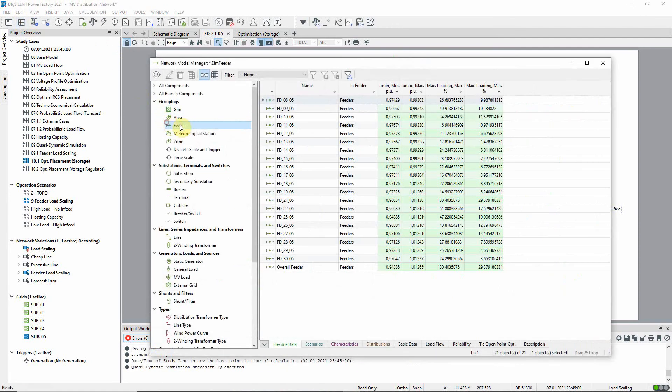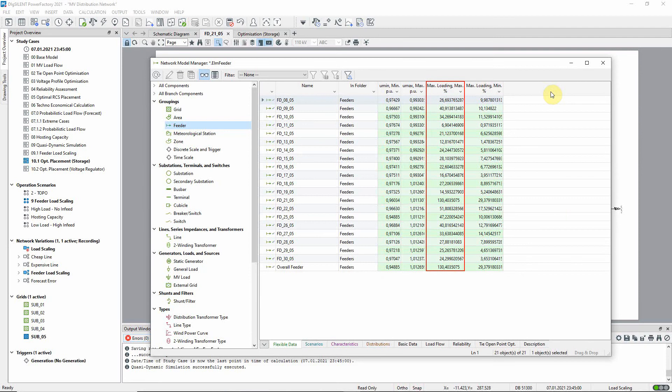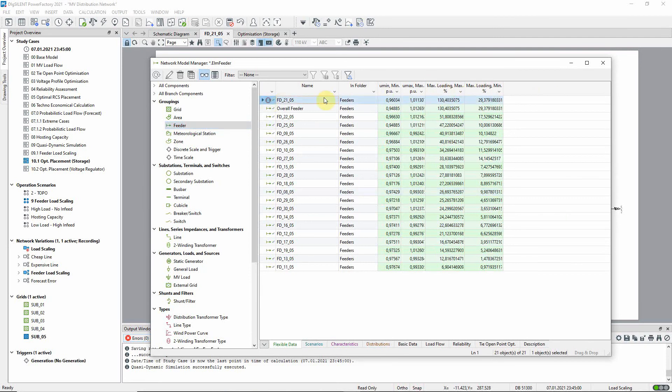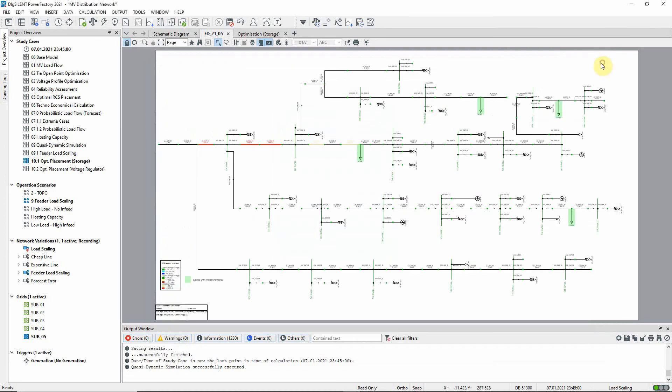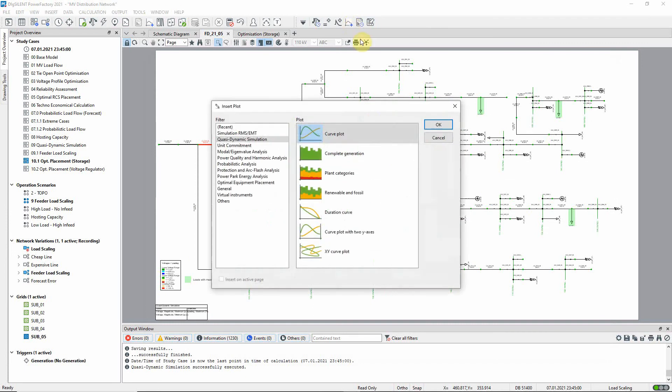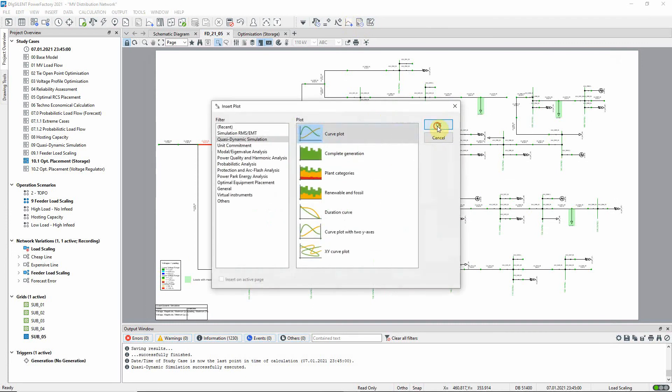Here in the network model manager we see the loading results in this column. The maximum value of max loading across the day is shown. Sorting on this column we see that feeder FD 21 5 is overloaded for at least part of the time. We shall therefore focus on this feeder.